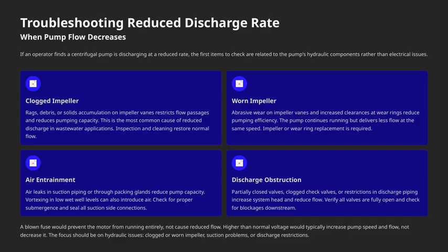Discharge obstructions are another factor to consider. Partially closed valves, clogged check valves, or restrictions further downstream in the discharge piping increase the system head, which in turn reduces flow. Always verify that all valves are fully open and inspect for any blockages downstream. It's important to note what these issues are not. For example, a blown fuse would prevent the motor from running altogether, and higher than normal voltage would usually increase flow, not decrease it. So, when troubleshooting reduced discharge, your main focus should be on hydraulic issues: clogged or worn impellers, suction problems, or restrictions in the discharge piping. That's where the problem usually lies.